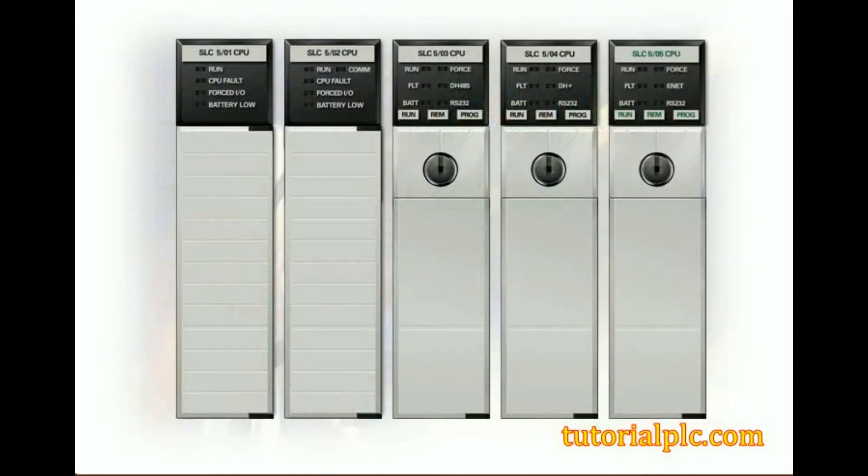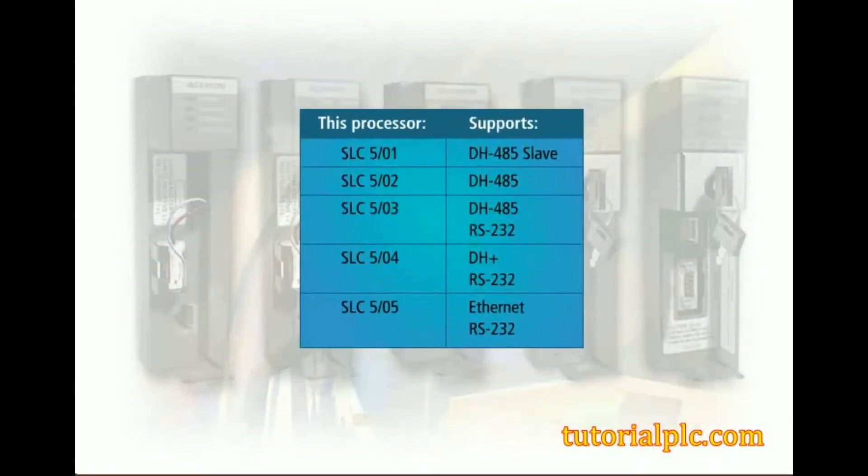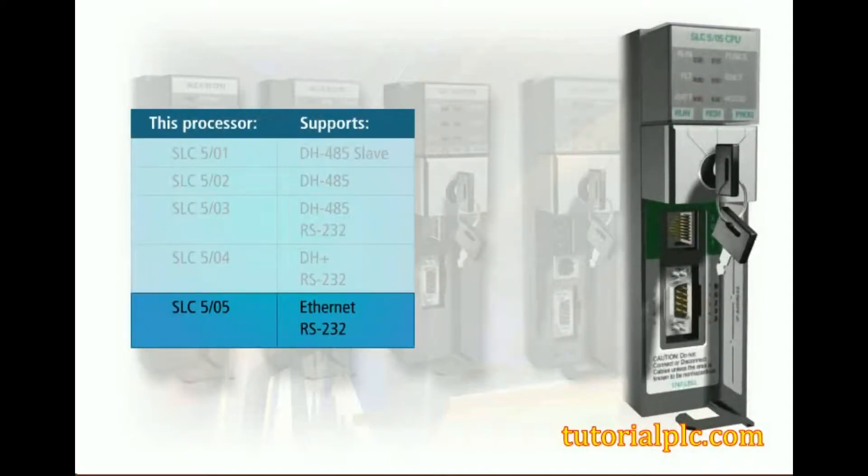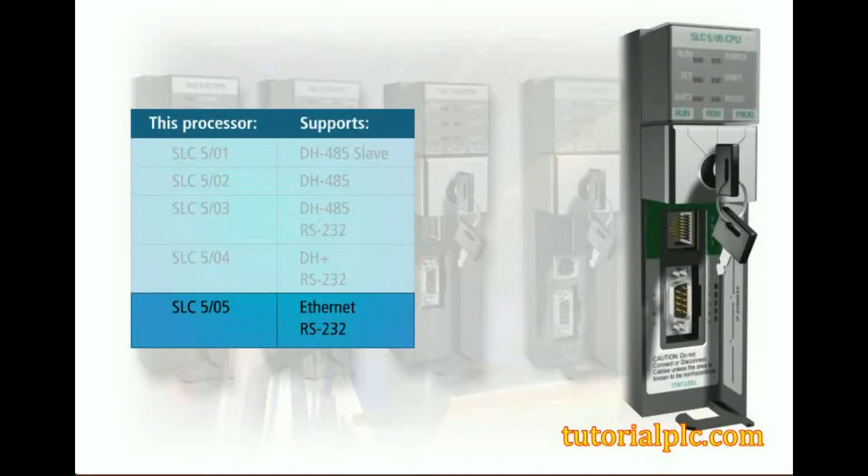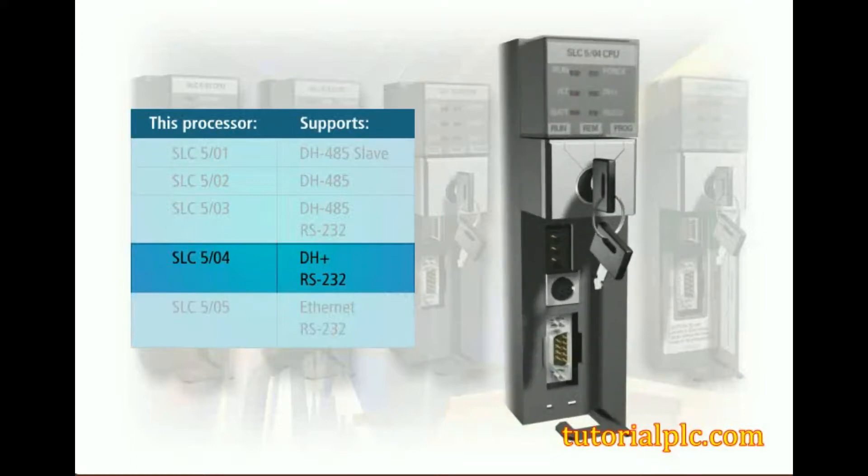Each SLC processor has built-in communication capabilities, but the capability varies by model. This chart displays the onboard communication capability of each SLC processor. Notice that the SLC 505 supports both Ethernet and RS-232 from its front panel communication channels, while the SLC 504 supports Data Highway Plus and RS-232 communications.